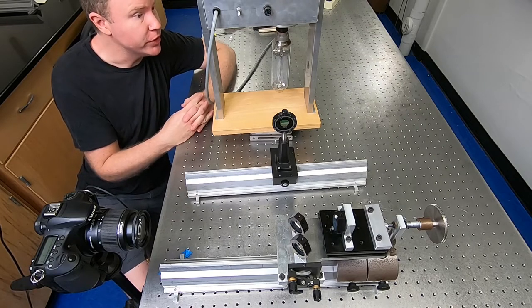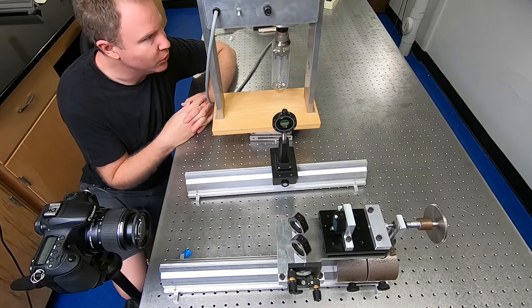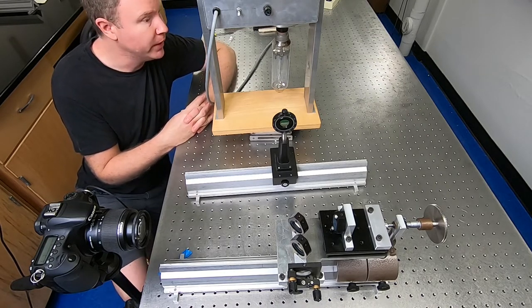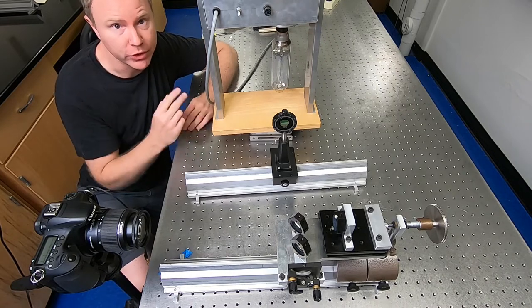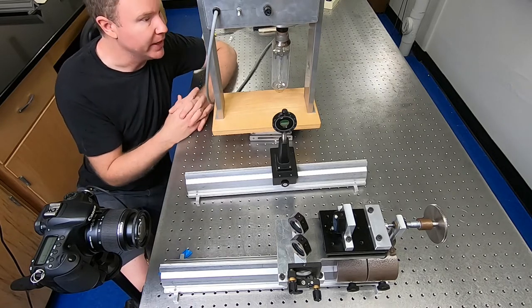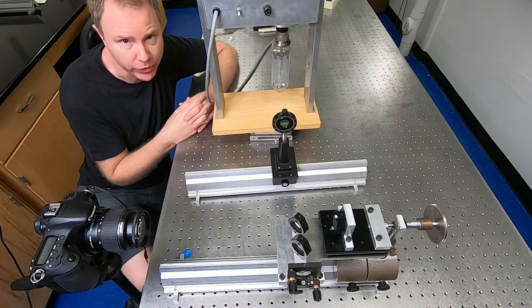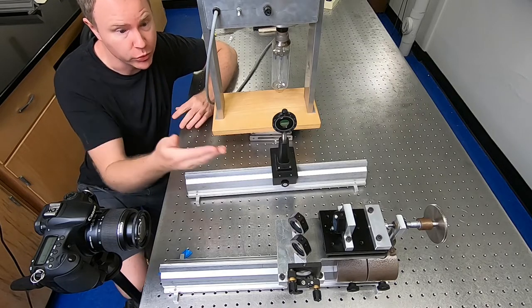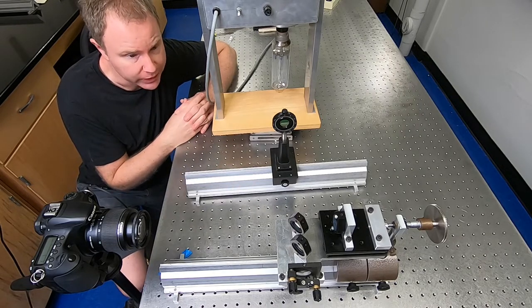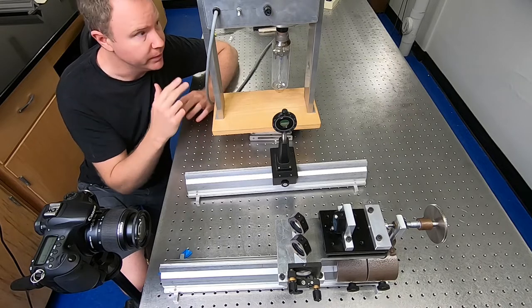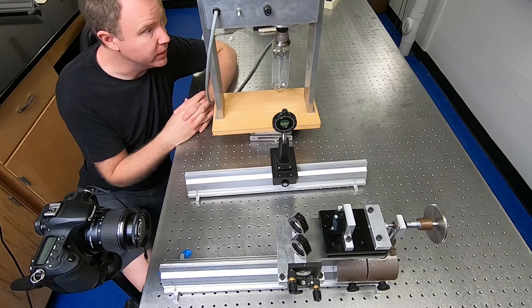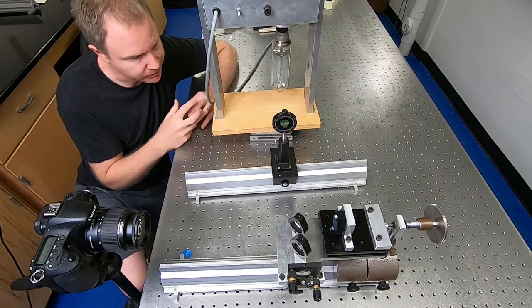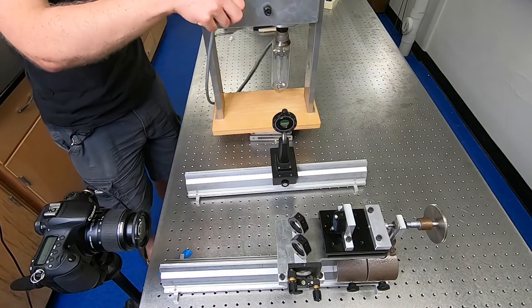The main emission of sodium, this sort of yellow orange-ish glow, is actually two spectral lines that are very close to each other. Less expensive spectrometers aren't able to resolve those two lines, but I'll show you a technique where we can accurately measure the distance in wavelengths between those two lines. Let me turn on the light and let it heat up.